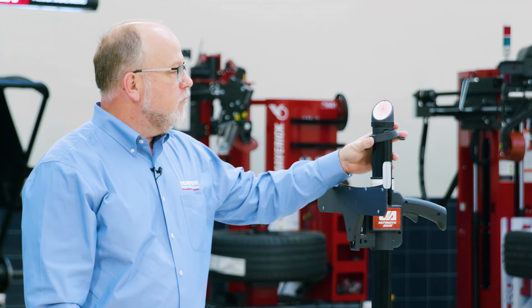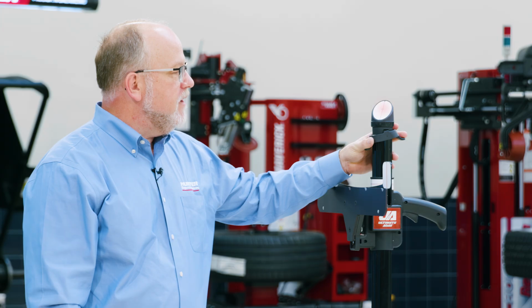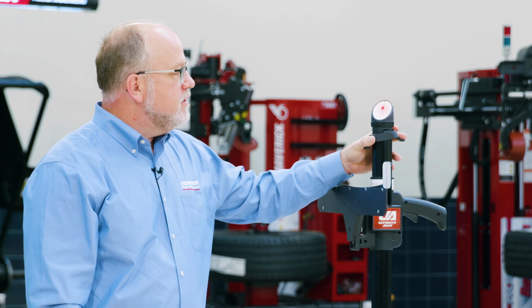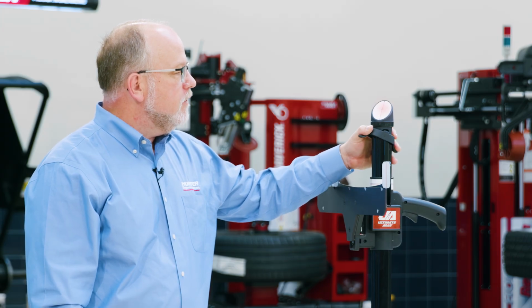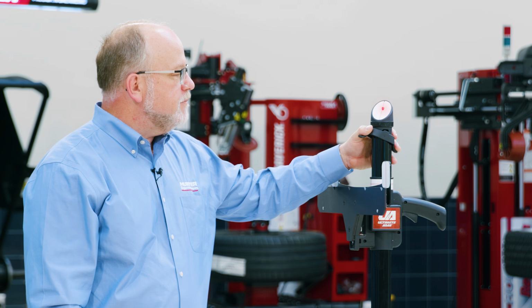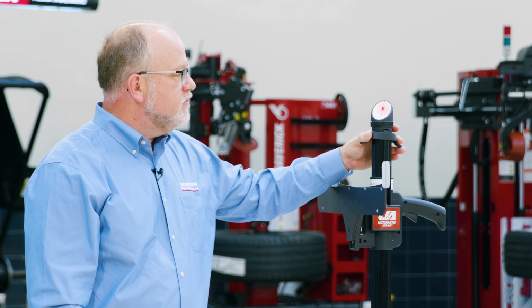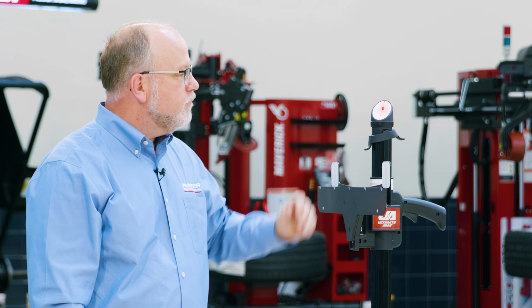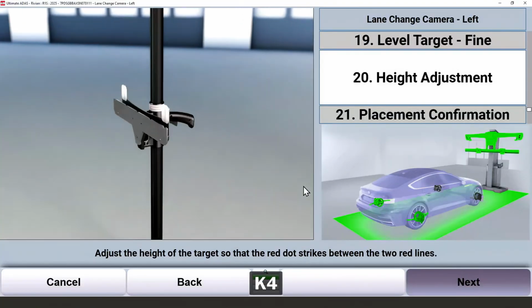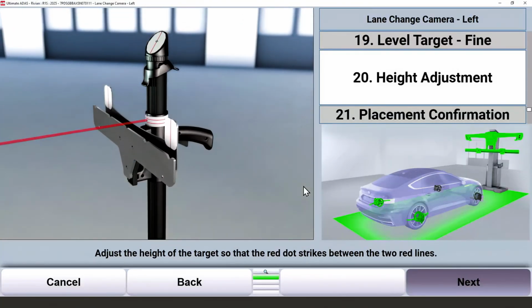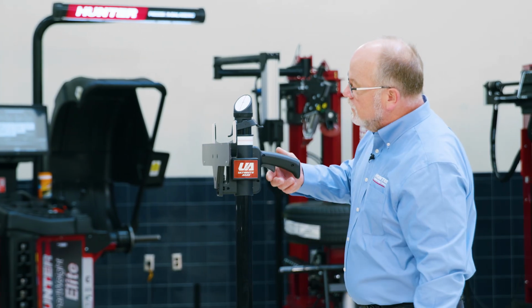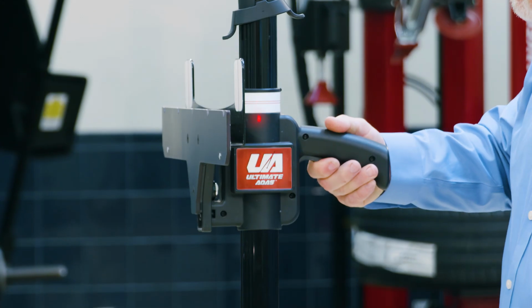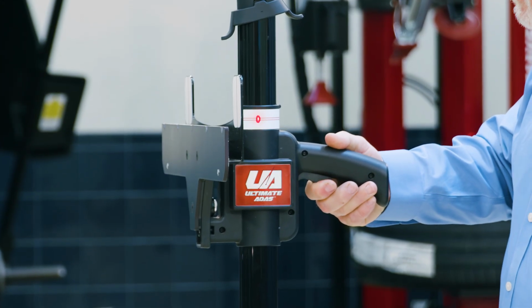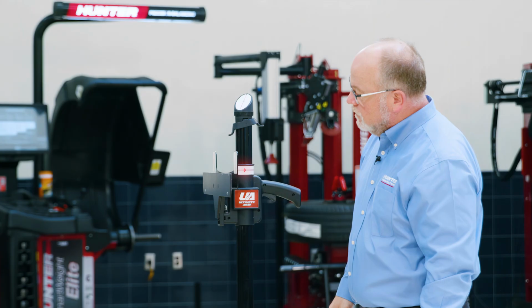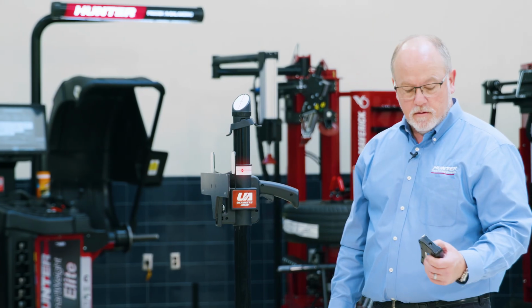At this point, the red dot laser will be flashing, making a measurement at each flash. Simply move up and down on the red vertical line until the flashing stops. Once the flashing stops, you've achieved fine level. Next, we'll do the height adjustment. We're going to bring that red laser into the collar here on our stand. We've achieved the correct height.